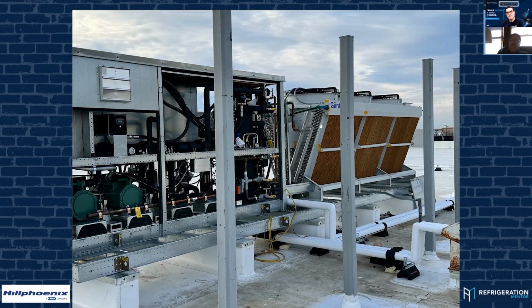The air can influence these things greatly, especially in the wintertime. We can put all the control we want in to try to keep the head pressure modulated, but if the wind's blowing through the condenser, whether the fans are on or not, you cannot control your head pressure. I've seen the wind blow through these things at minus 20 degrees where it actually sucked all the liquid from the rack into the condenser, and the rack shut down on the differential. The vessel and the rack actually became the same pressure, and the rack shut down. And once you do that, it's a tough scene to get that rack back up and running when all the pressure's equalized.